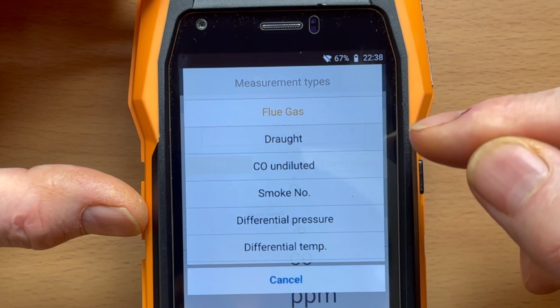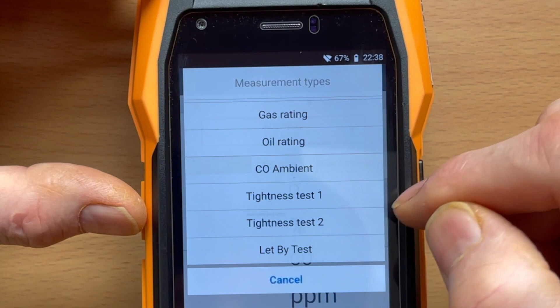So let's press cancel. If we go to the top now, you can see here we've got a flame. If we click on the flame, it says we can do flue gas in, draft, CO, smoke, differential pressures, and so on. You can pick whichever test you want to do, like tightness test and let by. We'll look at those later, but for now we'll do flue gas analyzing.